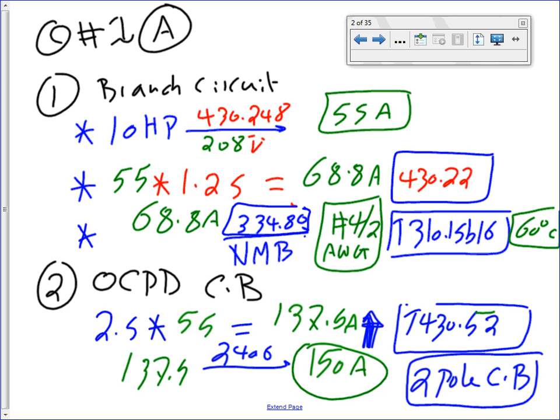Any comments, guys? Any questions? How to size the overcurrent protection device for it? Go up on the test, because sometimes you go up, sometimes you go down. Write yourself a note, guys: when we size the branch circuit for motors, go up on the overcurrent protection device.